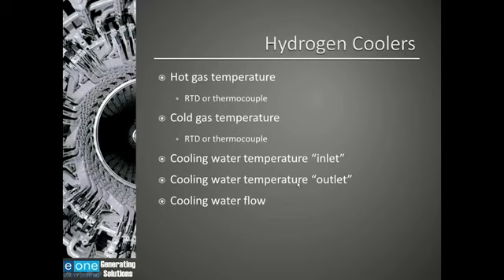One of the things that was not shown in the slides earlier on that P&ID were temperatures and the water flow. So I'm going to talk a little bit about the hot gas temperature. This is monitored by either an RTD or a thermocouple. The cold gas temperature, again, is monitored by either an RTD or a thermocouple. Cooling water temperature, the inlet of the cooling water temperature, the outlet temperature of the cooling water, and then the cooling water flow.